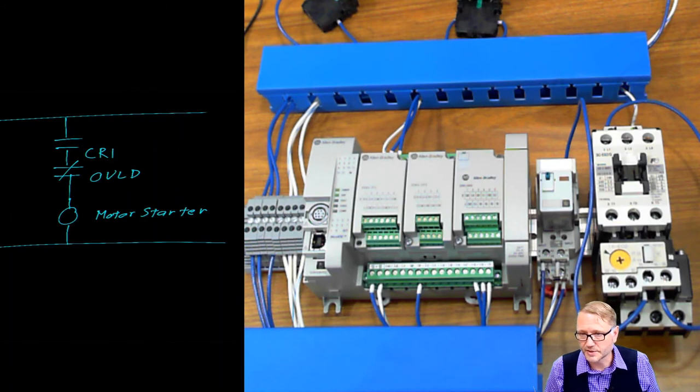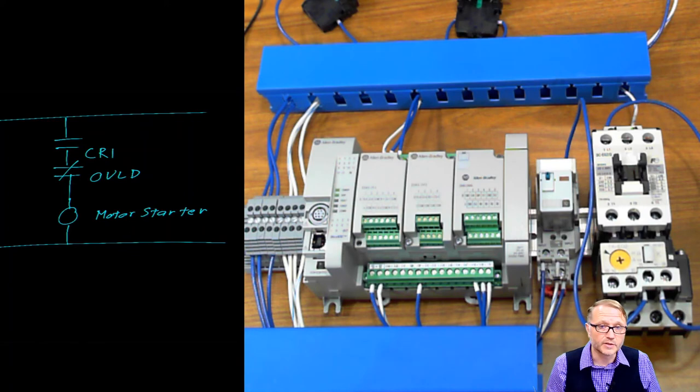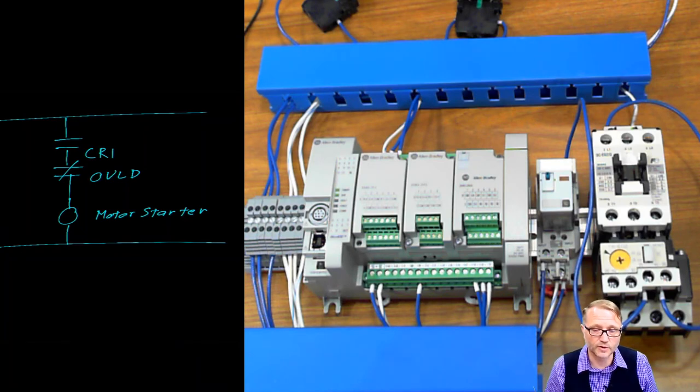There's any number of conditions that could cause this thermal overload to activate. The motor could be defective obviously. You could have a phase imbalance. Maybe one of your three phases doesn't have the right voltage or current on it which would cause the other two to overheat. You could have a brownout condition in which case the motor will pull more current. Let's see. What else? If you start and stop the motor too many times in a row it tends to heat up. So you've got to watch out for all those types of things. Or the motor could also be mechanically overloaded as well which would cause it to overheat.